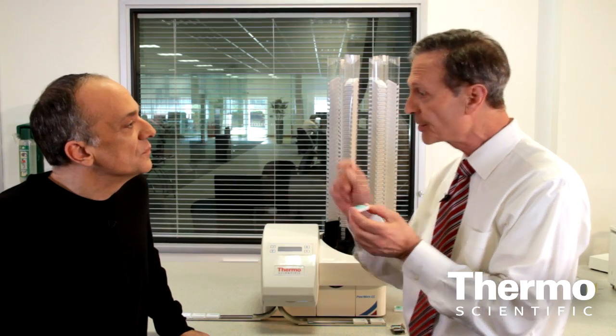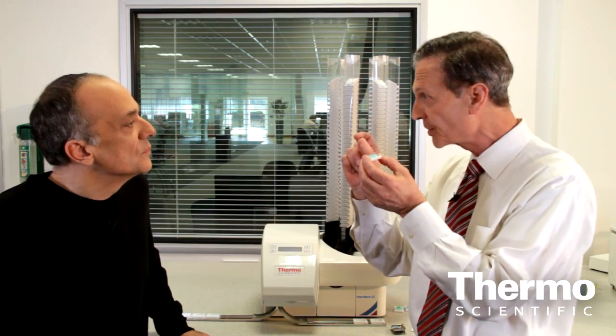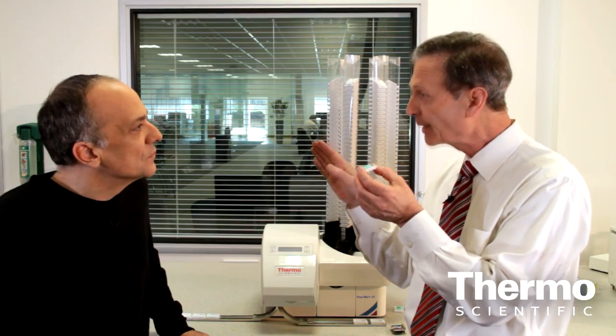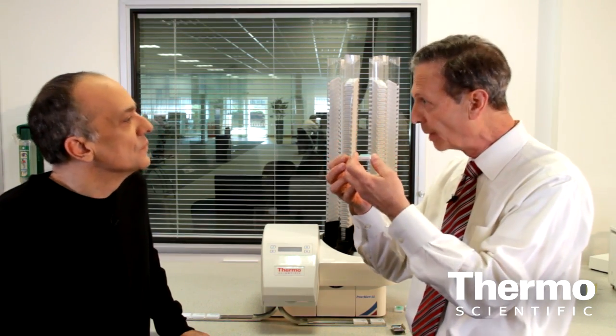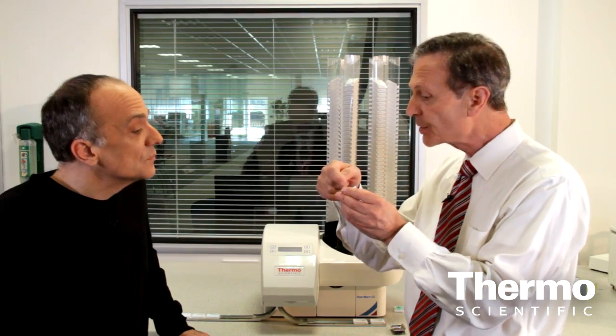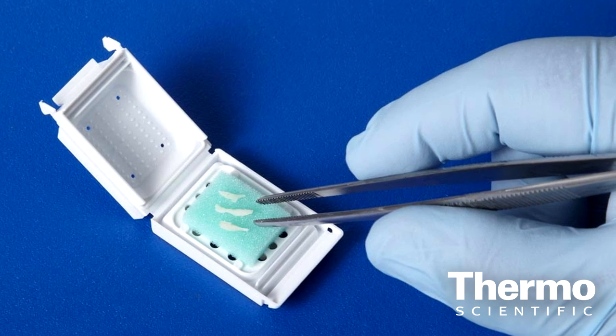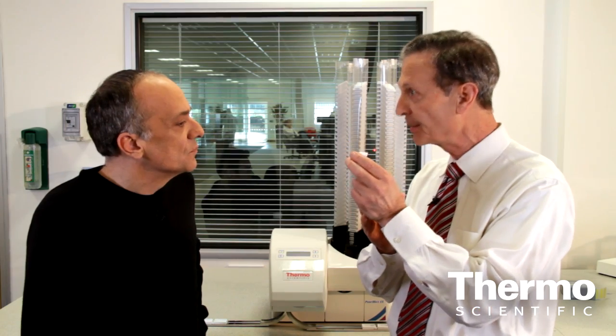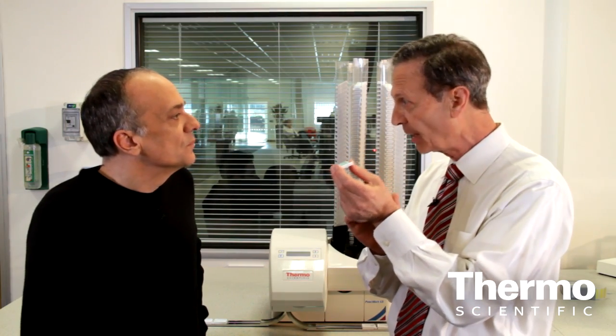For instance, there are very small biopsies which are called needle biopsies which look like little threads. In a standard cassette, they squiggle up like worms. You've got to straighten them out. That takes even longer and ends up with a messy specimen. In this, we can simply lay them on the foam. They're held firm and therefore you end up with nice straight sections on the slide. Big quality improvement. We've cut about 50% of the labour out of this process here.